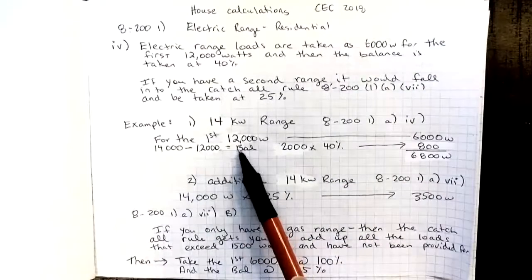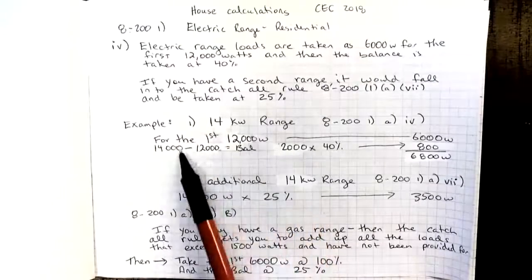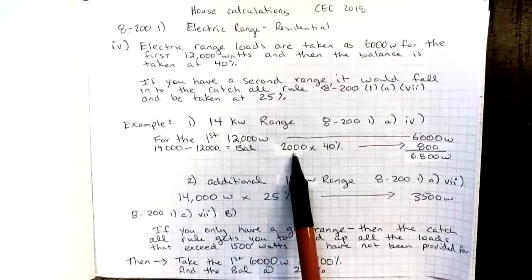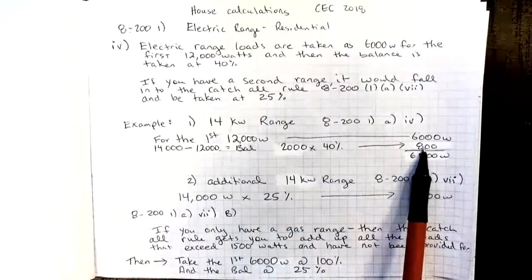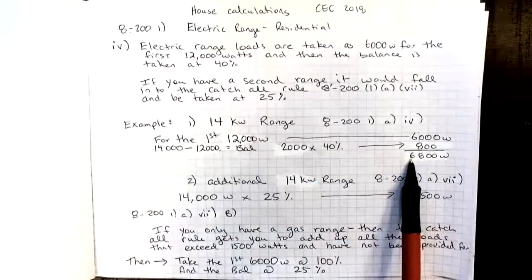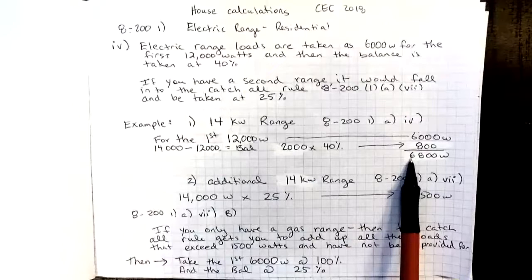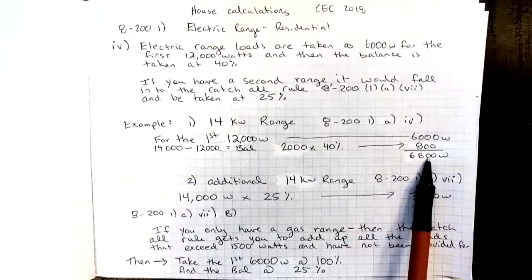Then the remaining, or the balance, is 14,000 minus the 12,000, gives us 2,000 left over. We apply that at 40%. And so our total demand factor towards the service for the first range would be 6,800 watts.